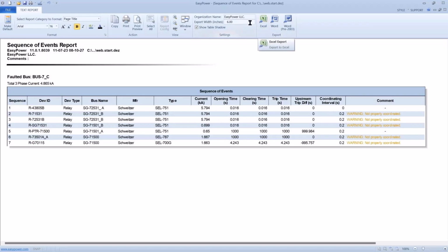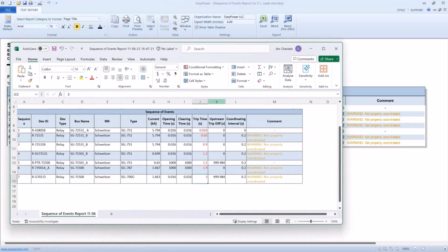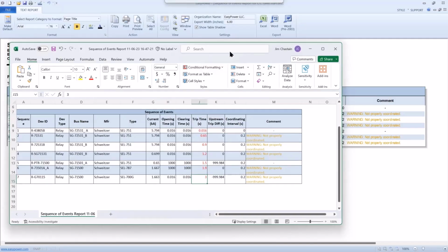Now what I'm going to do is export this to Excel, and it looks something like this. Then I'm going to insert a trip time column. This is where I'm expecting to have this relay, for this particular current level, allow for about a 300 millisecond separation, considering we have breakers opening at different voltages. So coordination looks like it's about 300 milliseconds per step. Again, that's just an arbitrary number. Probably the minimum would be 200 milliseconds. Let's stay with this.